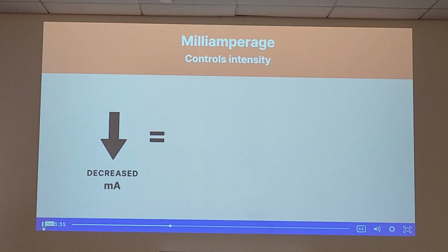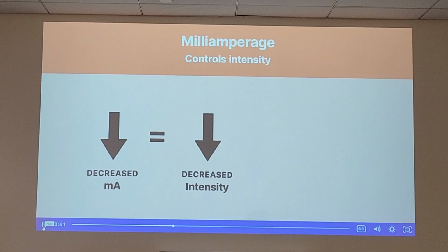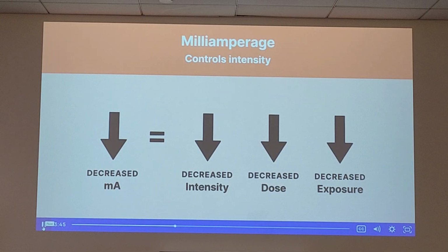The reverse is also true. If we decrease the MA during a CT exposure, that will decrease the intensity of the X-ray beam, it will decrease the dose to the patient, and it will also decrease the exposure to the detectors.